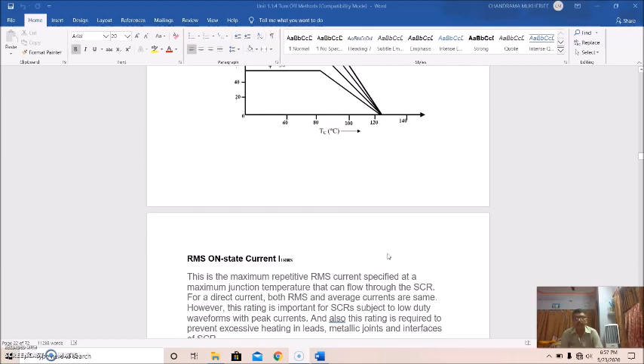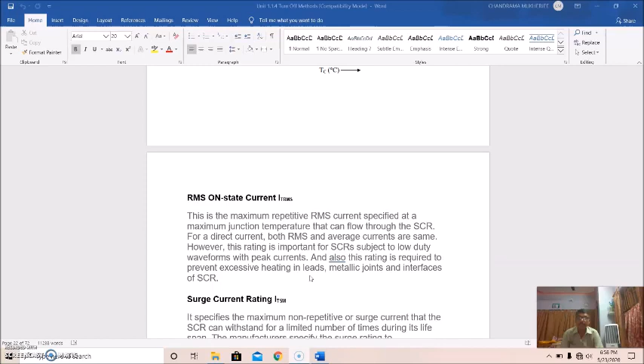Now the RMS on-state current, IT RMS. This is the maximum repetitive RMS current, specified at a maximum junction temperature, that can flow through the SCR. For a direct current, both RMS and average currents are the same. However, this rating is very important for SCRs subject to low duty waveforms with peak currents. It is also required to prevent excessive heating in leads, metallic joints and interfaces of the SCR.